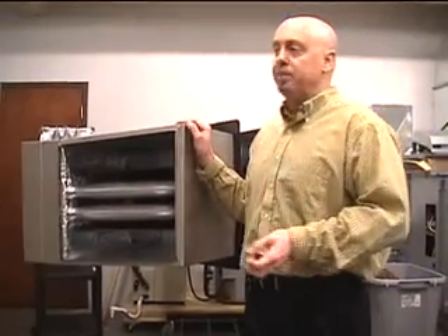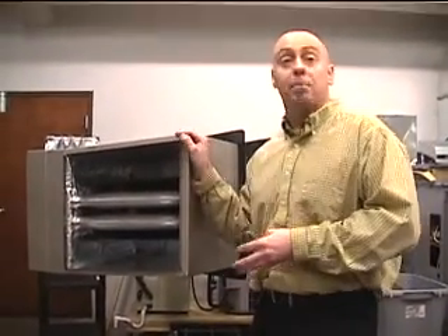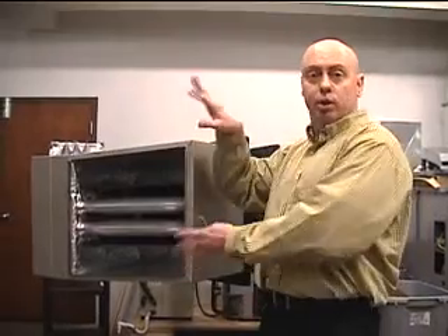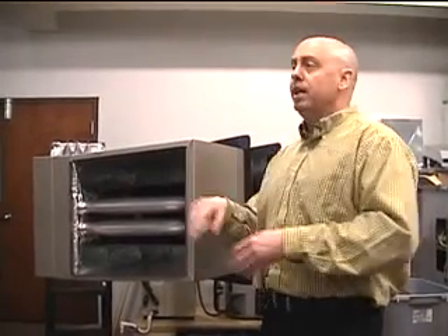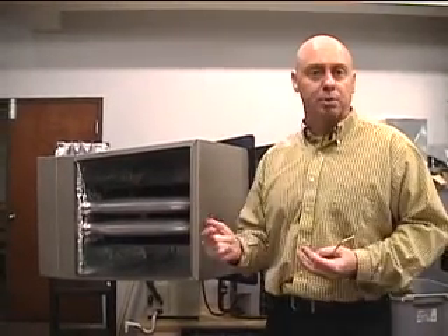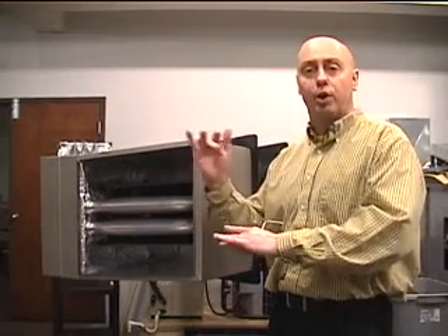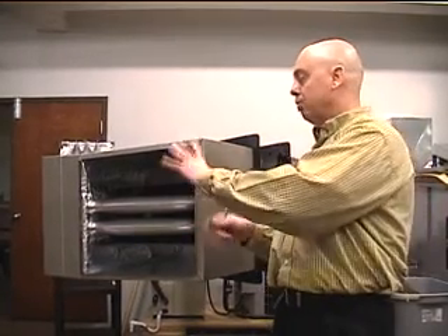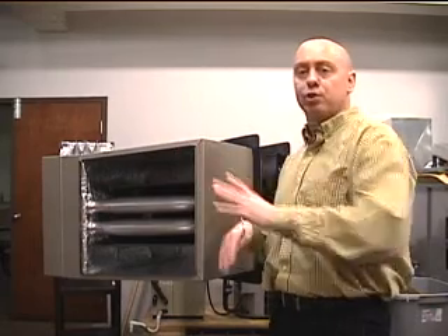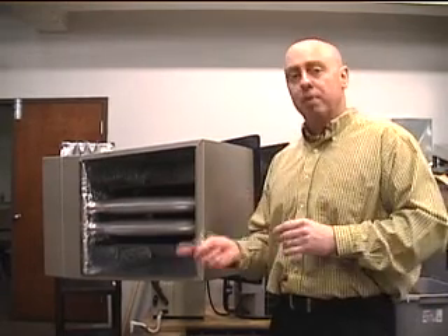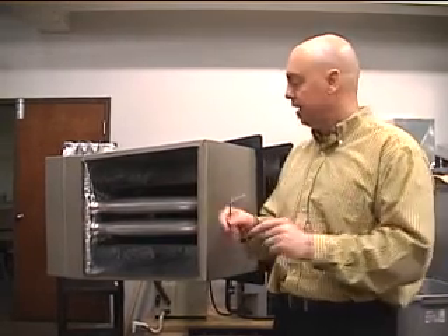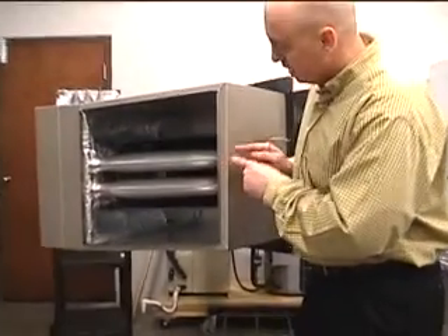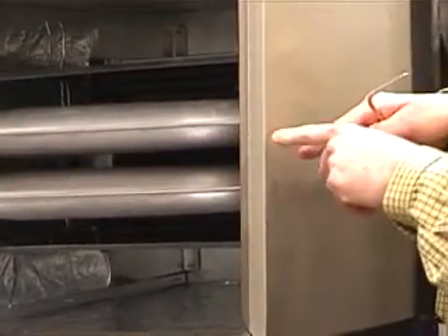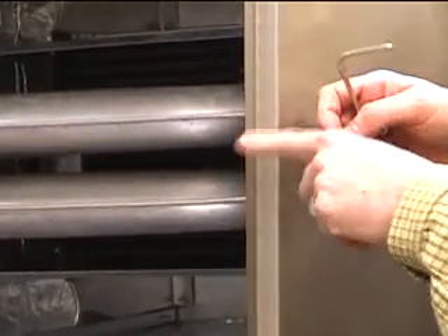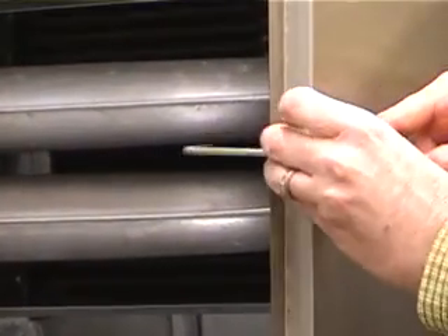Now, a lot of guys will say to me, I understand that on a lot of applications, you have a case coil sitting directly on top of the furnace. So, although that's a testing area and I set it up so we can test that there is separation between the coil and the outlet of the furnace, I realize that is not always the case. A lot of times you will have a coil sitting directly on top of the furnace. When you run into those cases, one good place to get the reading between the coil and the furnace is actually the back side of the furnace. A lot of times I can tap the back of the furnace up at the top area, and I can actually get the probe and tap it in like this.